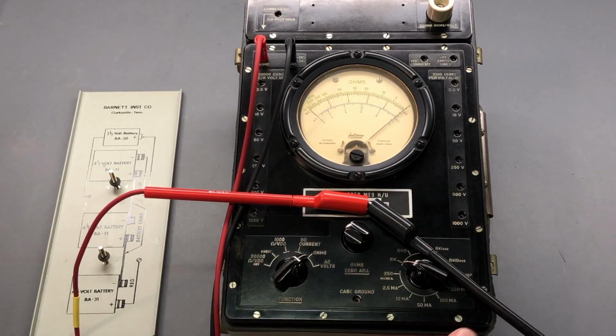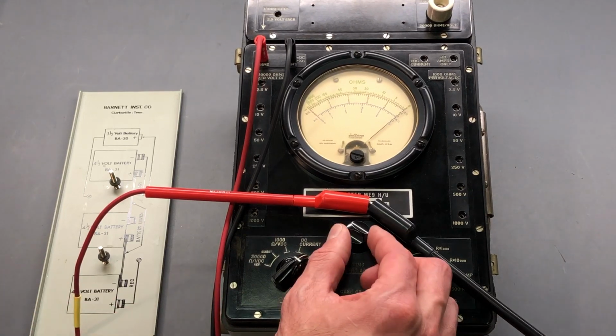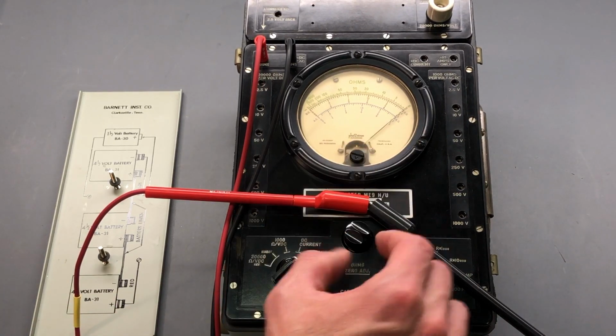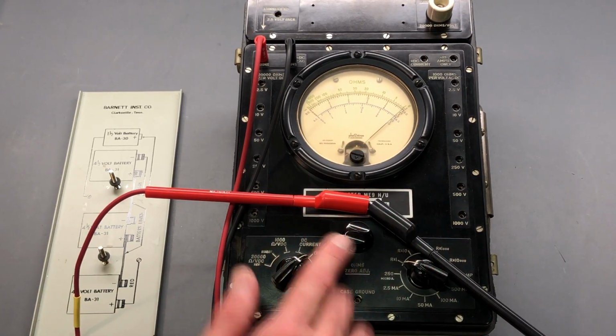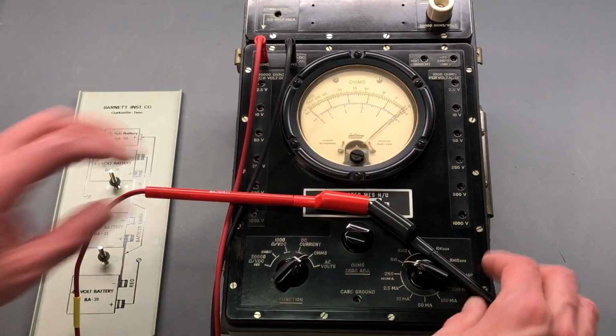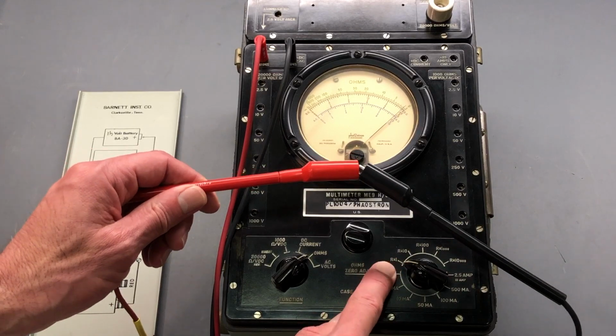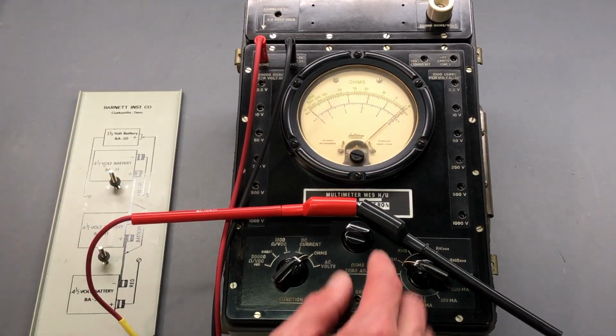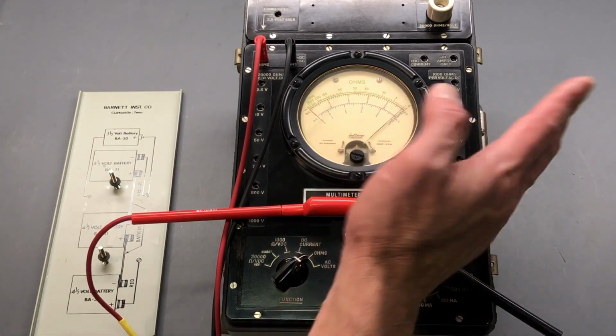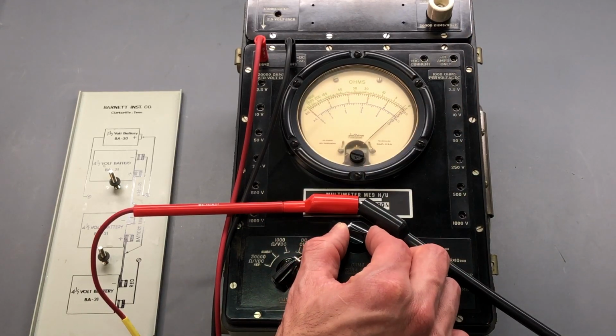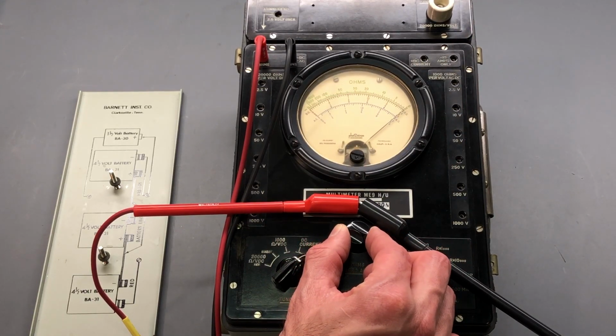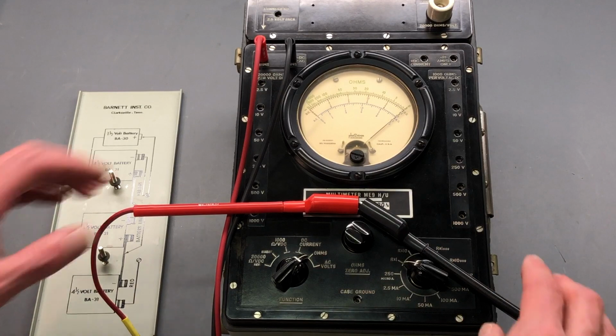When you first put the lithium in and it's very close to 1.8 volts, you'll find that even with this turned all the way down, it'll be off scale, too high. But if you short the leads together on R times 1, which draws the most current, give it a minute or two, things settle in, and it comes into range so you can zero it. You can see it's right on 0, no problems there.